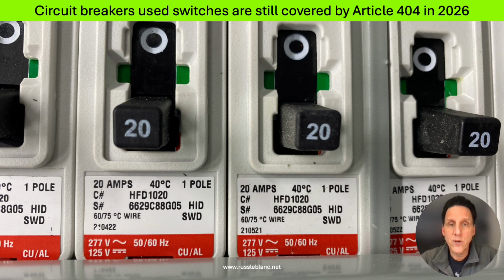In the morning, the employees would come in and just flip on the circuit breakers for the lights, turning all the circuit breakers on in the panel. All the lights in the store stay on all day. And then when the employees leave, they shut off all the circuit breakers just as if they were wall switches. And that's fine because these circuit breakers are rated for that kind of use, switch rated. These are covered by 404.